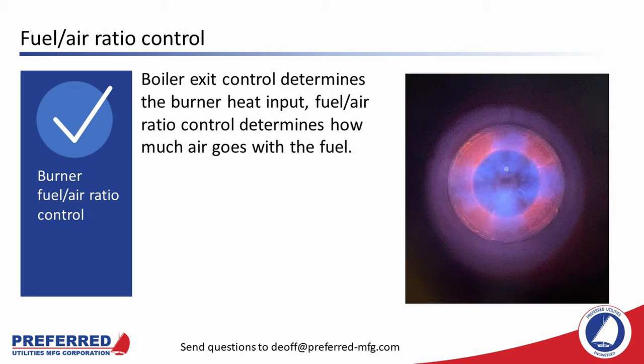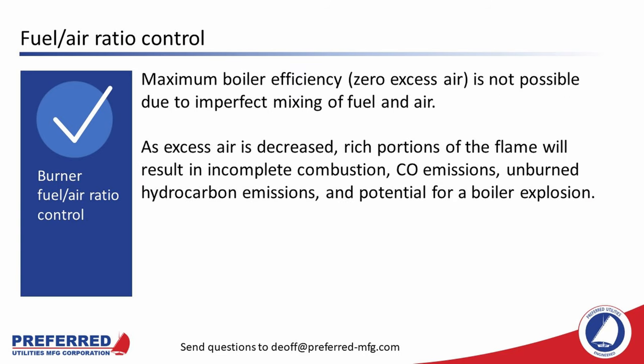Boiler exit control determines the burner heat input; fuel-air ratio control determines how much air goes with the fuel. Pictured at right is a nice-looking flame from a Preferred API low-NOx burner. Maximum boiler efficiency is at zero excess air. However, this is not possible due to imperfect mixing of fuel and air. As excess air is decreased, rich portions of the flame will result in incomplete combustion, CO emissions, eventually unburned hydrocarbon emissions, and the potential for a boiler explosion. Excess air is the largest efficiency loss for most boilers because the air we burn is about 79% inert.